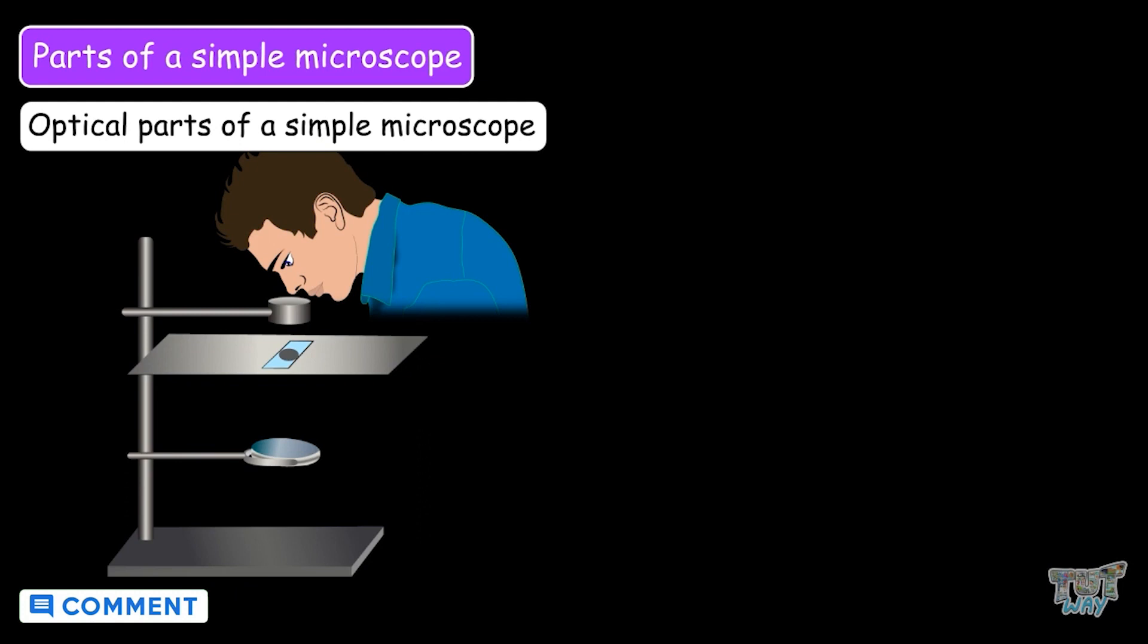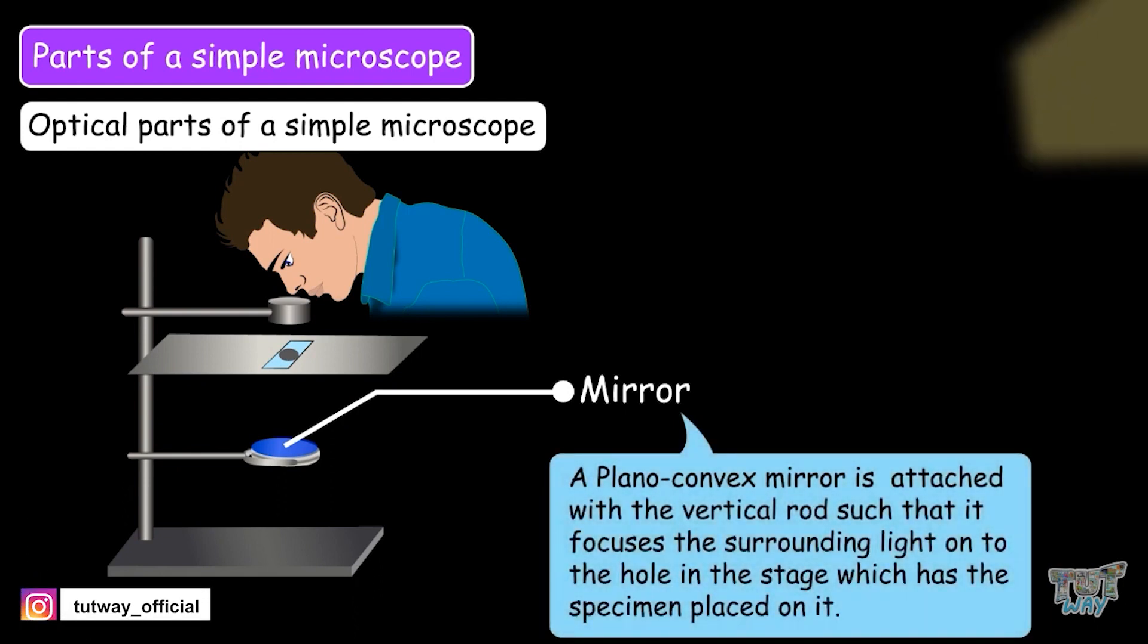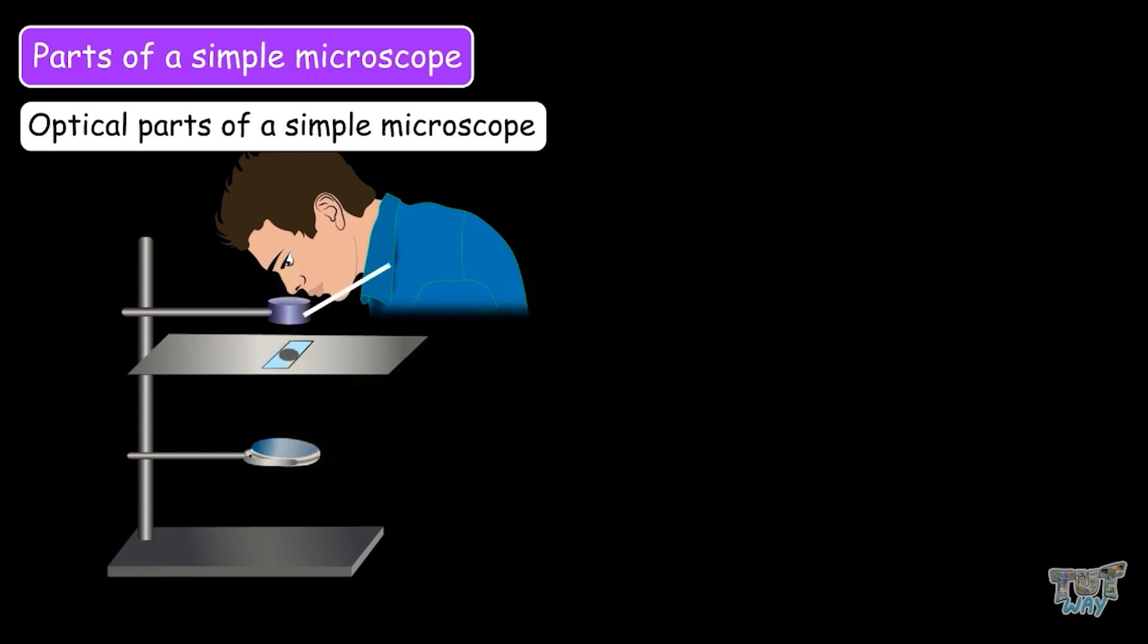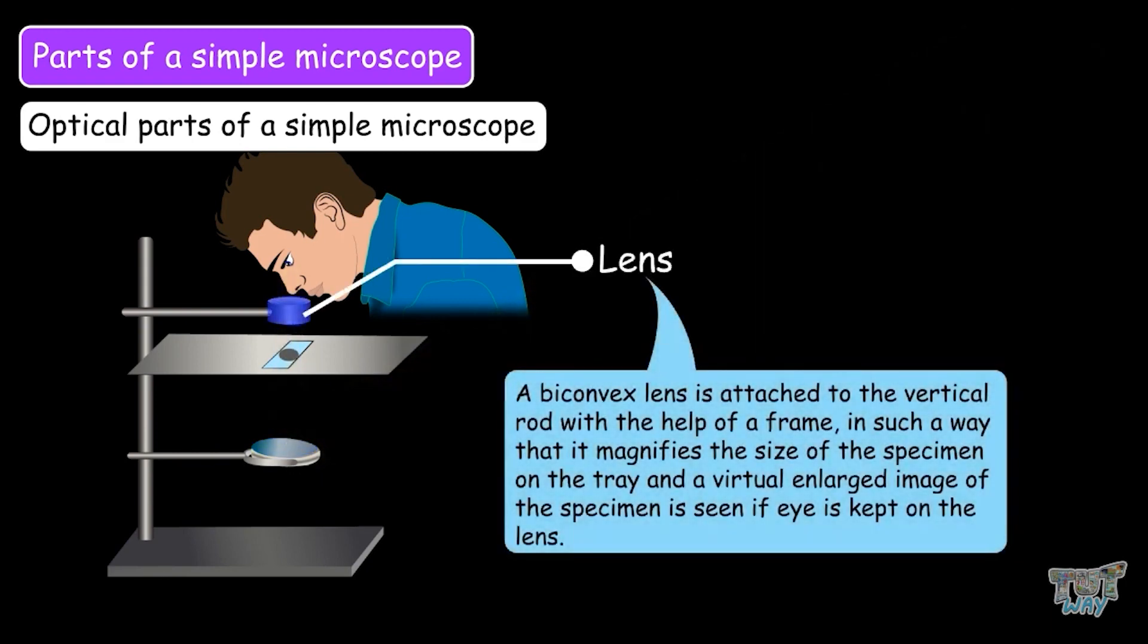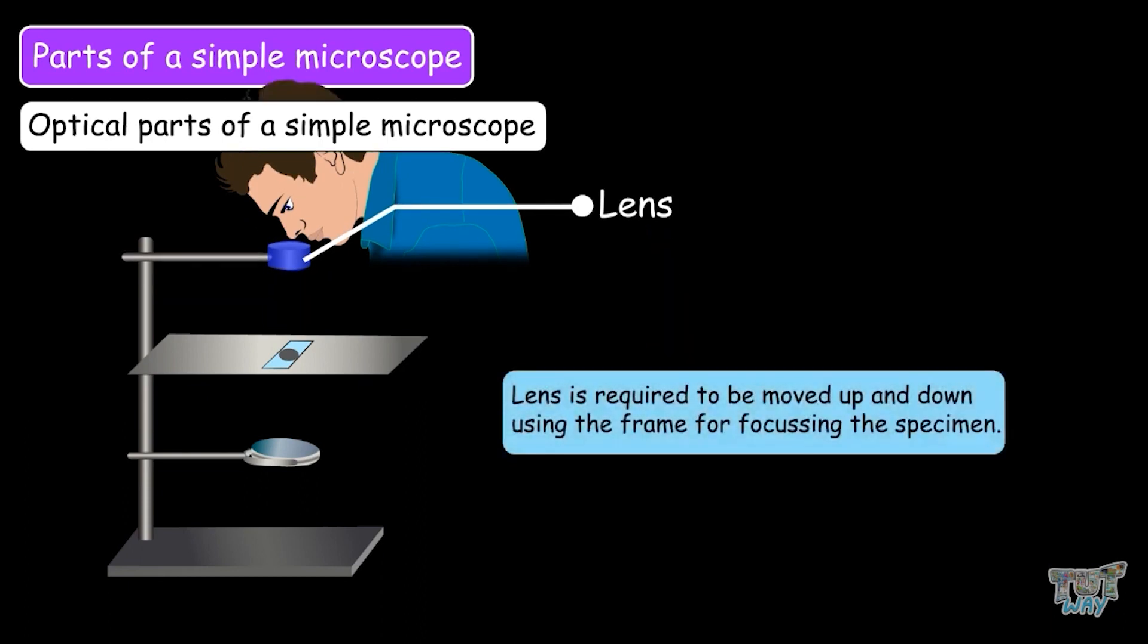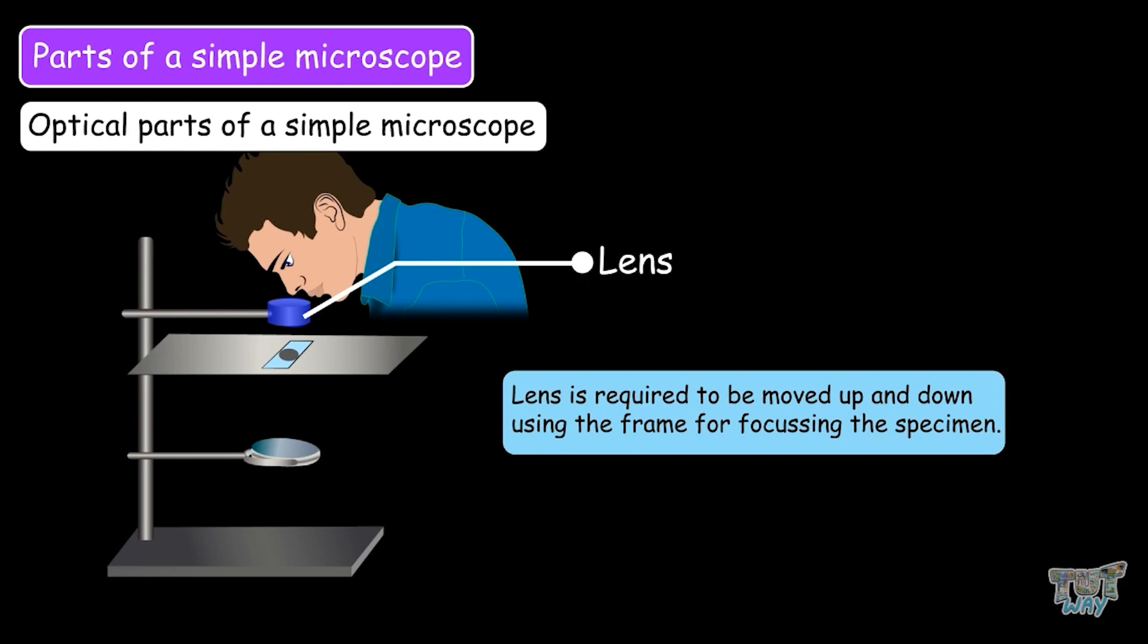Now let's learn the optical parts of the simple microscope. First one is the mirror. A plano-convex mirror is attached with the vertical rod such that it focuses the surrounding light onto the hole in the stage which has the specimen placed on it. Second is the lens. A biconvex lens is attached to the vertical rod with the help of a frame in such a way that it magnifies the size of the specimen on the tray and a virtual enlarged image of the specimen is seen if the eye is kept on the lens. The lens is required to be moved up and down using the frame for focusing the specimen.